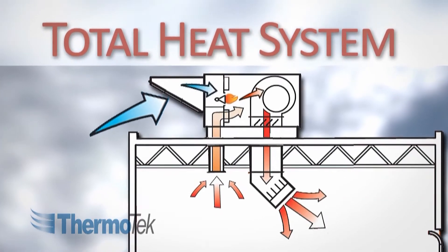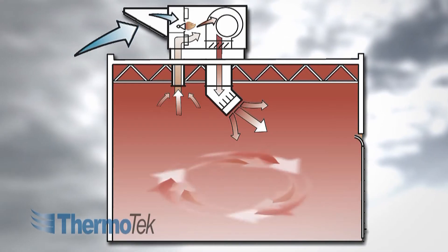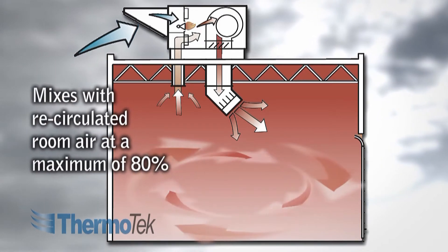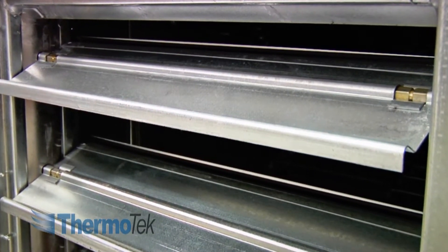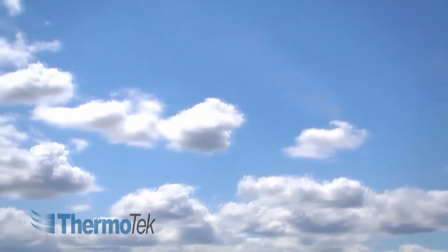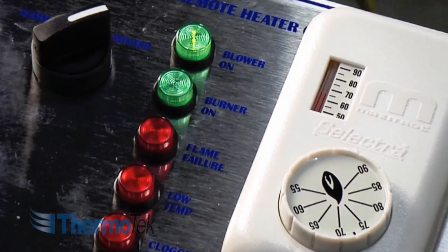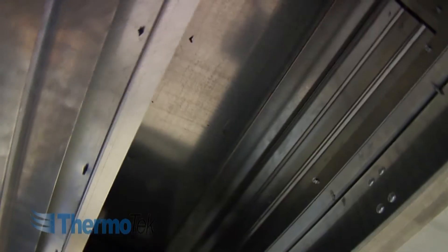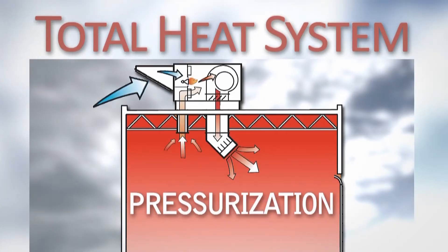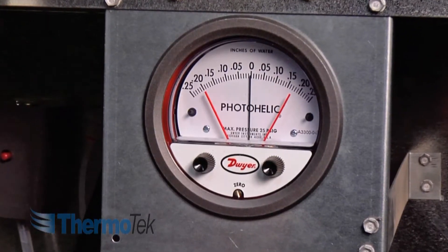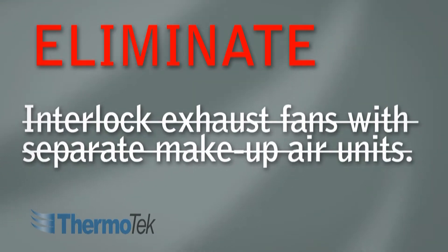The recirculation total heat system supplies at least 20% fresh outside air into the building and mixes with existing room air at a maximum of 80%, with the return air fully bypassing the burner. A building static pressure controller modulates the interlinked outdoor and return air dampers, introducing more fresh air as the building's exhaust and infiltration load changes. The recirculation system is simple to operate and maintain, with both heating and fresh air capabilities combined into one unit. With its ability to control building pressure, the total heat system automatically manages fresh air percentages and space or discharge temperatures, eliminating the need to interlock exhaust fans with separate make-up air units.